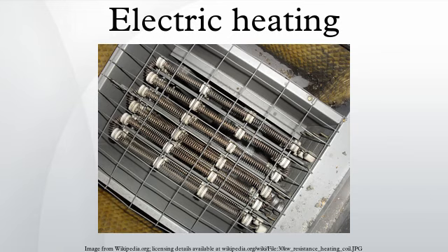To control the temperature of the water, a probe inserted alongside the element triggers a switch according to the temperature of the water, the system as a whole constituting a thermostat. Domestic immersion heaters. Domestic immersion heaters, usually rated at 3 kilowatts and on a 1.5 inch British Standard pipe screw plug in the UK, run on the normal domestic electricity supply, but consumers may also take advantage of a cheaper, off-peak electricity tariff such as Economy 7.